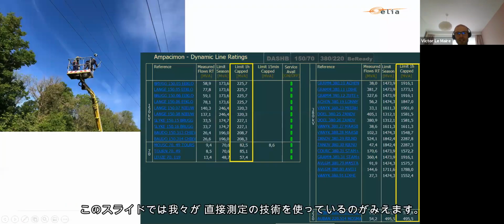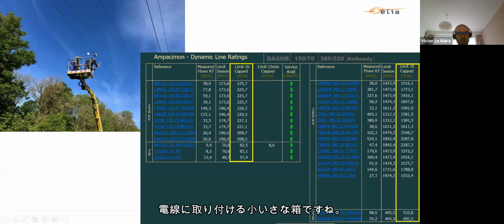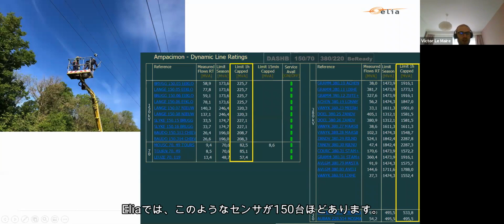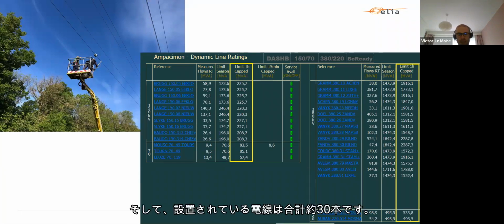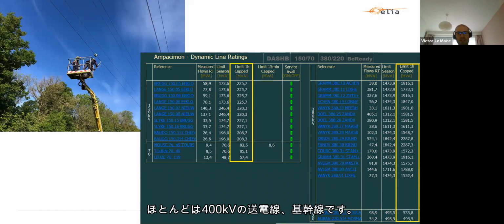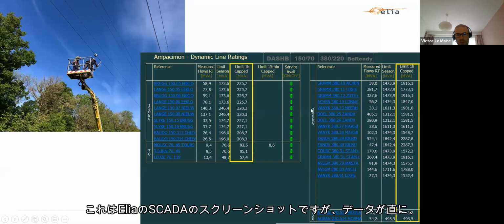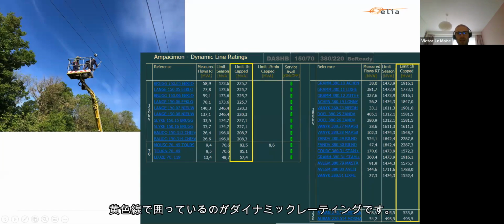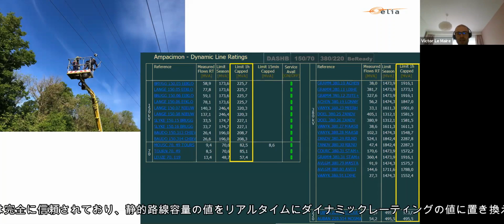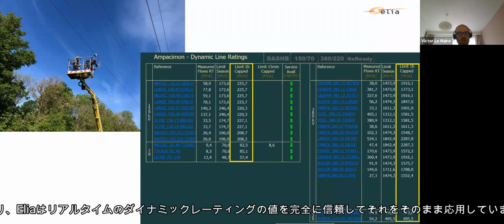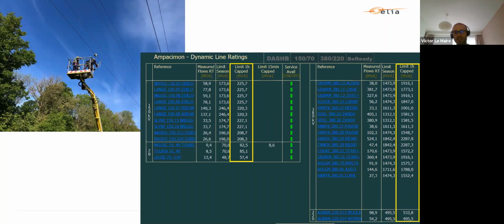Here you can see we are using direct measurement. The Ampacimon technology is a small box installed on the line. For Elia we have about 150 boxes installed, covering a total of about 30 lines, most of them 400 kV lines, the backbone of the grid. This is a snapshot of Elia's SCADA system, and what's shown in yellow is the dynamic values, which are fully trusted, replacing the static rating live. So Elia is making a full commitment, trusting those values live.